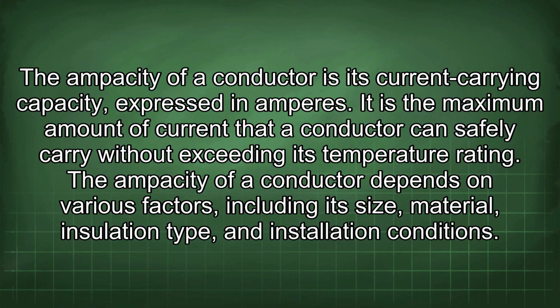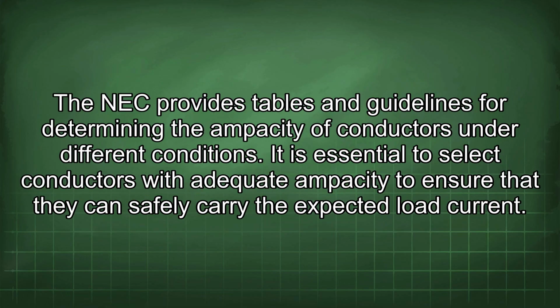The ampacity of a conductor depends on various factors, including its size, material, insulation type, and installation conditions. The NEC provides tables and guidelines for determining the ampacity of conductors under different conditions. It is essential to select conductors with adequate ampacity to ensure that they can safely carry the expected load current.